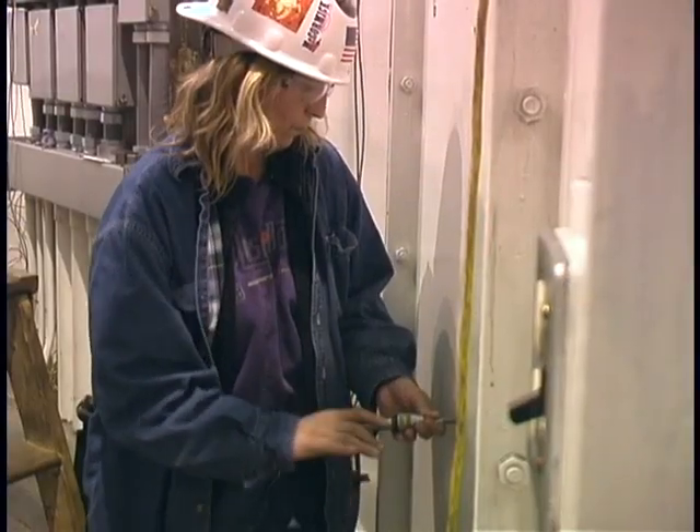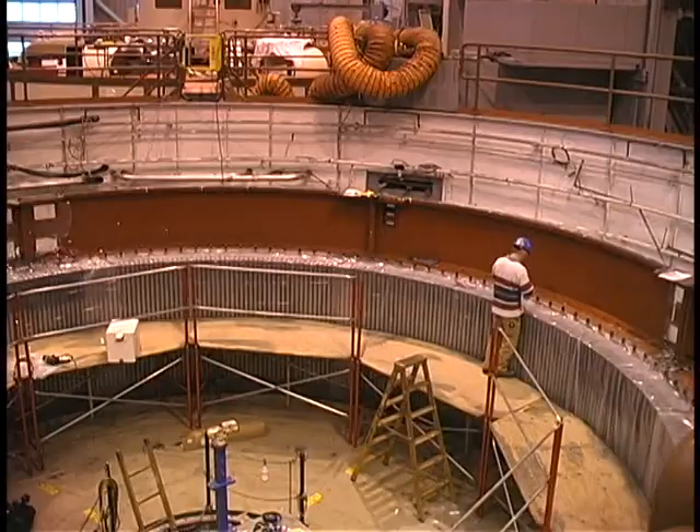Tearing down the machine took a couple of months. Julie Knopf is an electrician constructor who has been working on the rebuild with other City Light workers and a specialized outside contractor since April 2004. It's a major job — we're rebuilding the inside of the generator. They're restacking the iron and we're getting all new coils, which is how they produce the electricity.